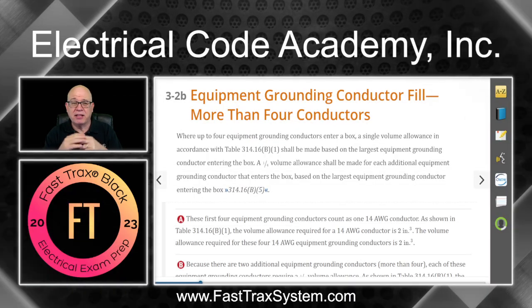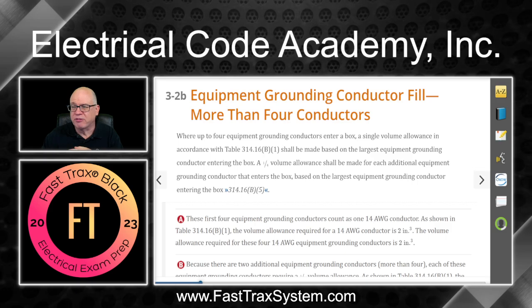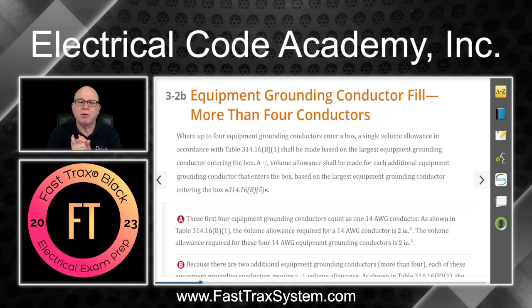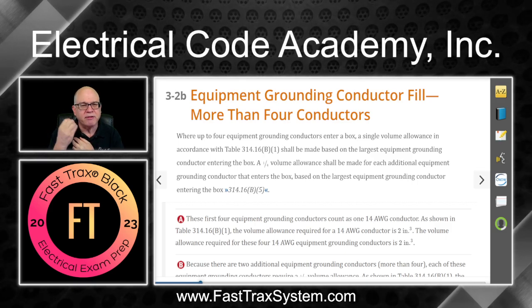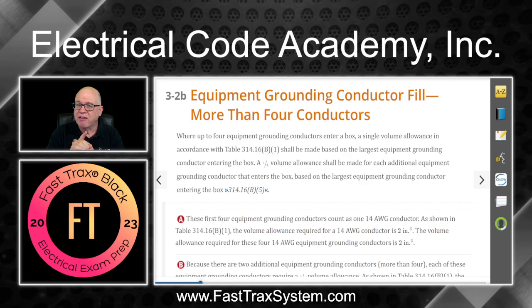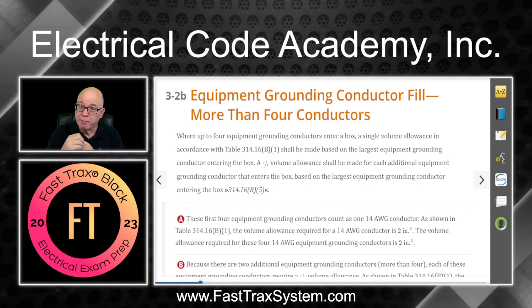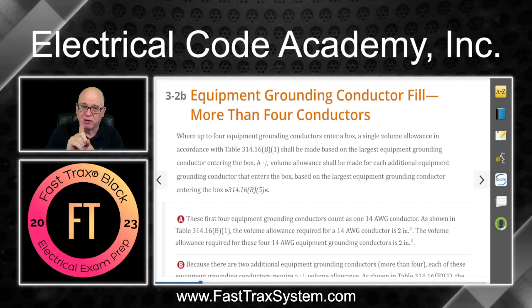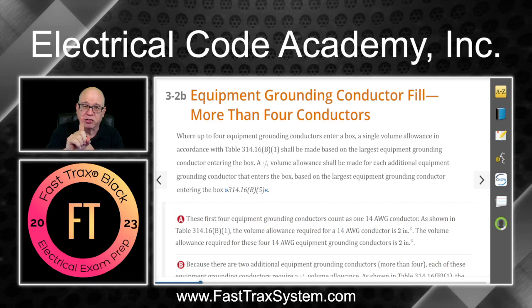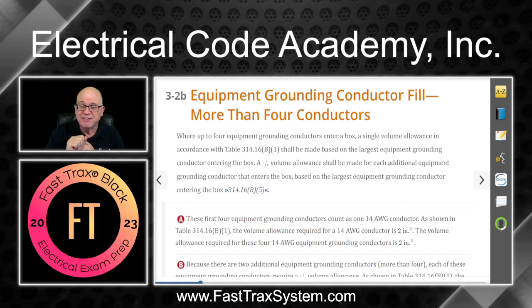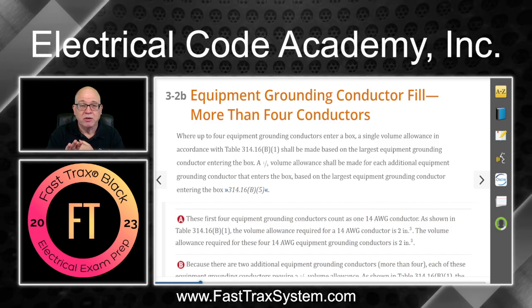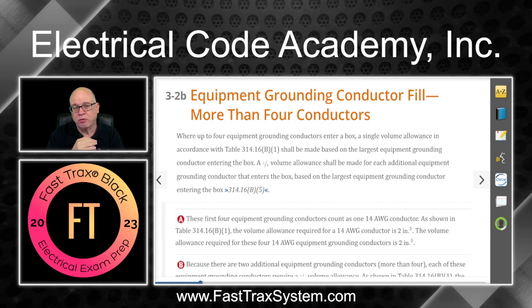So you should be in 3-2B of your Fast Trax program. And what we're dealing with is the equipment grounding conductor. We're working the volume again, but now we have more than 4. Because remember, up to 4, it's just one volume count. So it basically counts like one conductor when we're doing volume. But in this case, we have more than 4. We have to account for that additional volume.